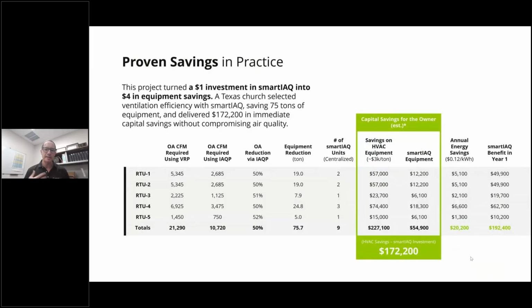Okay, so that brings me up to now. Let me show you this in practice. Let me show you where this really applies as it relates to savings. And I'm going to talk a lot here about first cost savings, but I'll point a little bit to energy savings. This is a church that happened to be in Texas. You could see in that third column, because as you can imagine, again, large places of assembly, a church obviously has a big sanctuary, we were able to provide a reduction of outdoor air around 50%, which came to a reduction in the equipment load of about 76 tons.